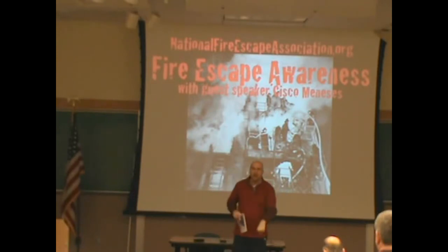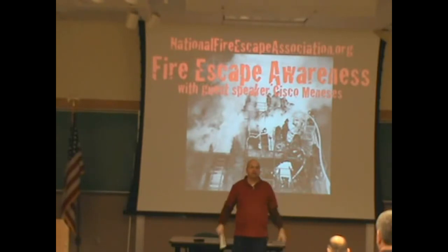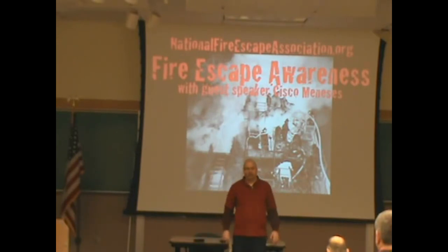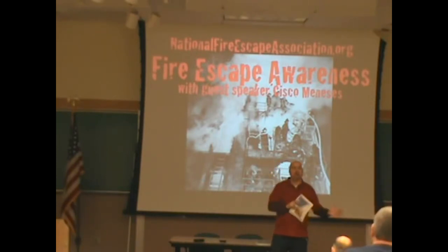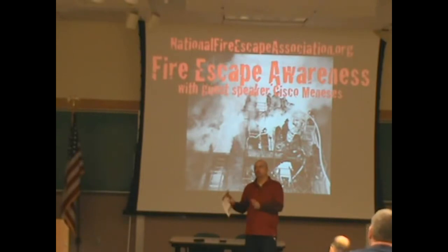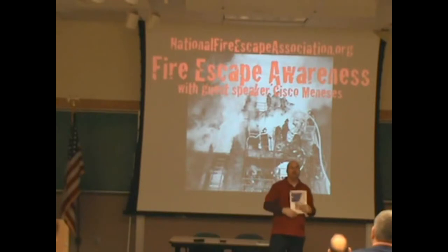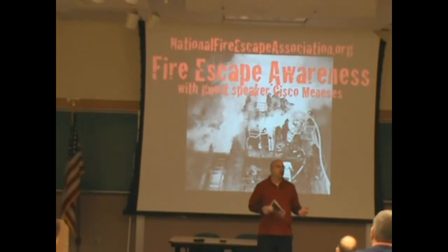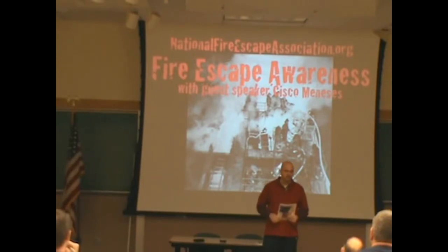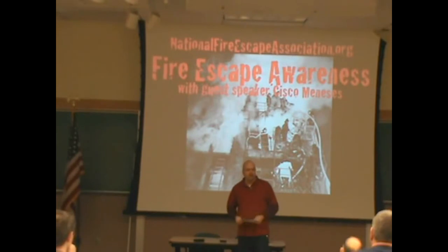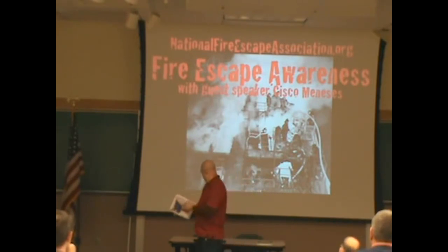One of the advantages to refurbing today is that you're going to put off load testing for the next 15 to 25 years, because it will be considered other evidence of strength. If you give me a 15-year-old fire escape today, I can sign off for you and say other evidence of strength is that the bolts are 10 to 15 years old, the fire escape is in pristine condition, it was all galvanized with a 50-year warranty. On fresh new fire escapes, you'll either do a load test or do other evidence of strength.